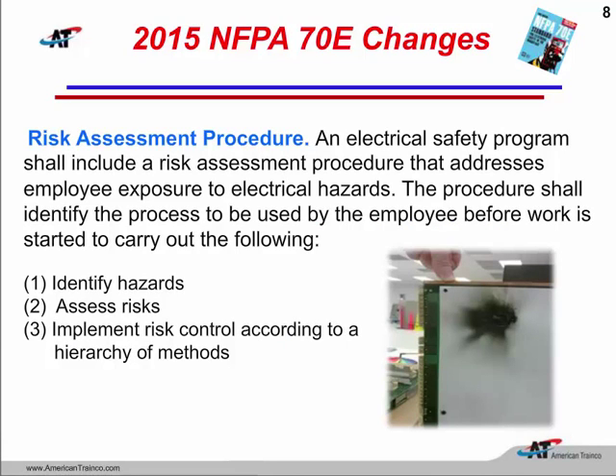So here's the risk assessment procedure. It does have to be included into the electrical safety program, and of course we're going to have to first identify the hazards. So we've got to take a look at the piece of equipment that we're about to approach, and we have to make a determination: is there any shock, arc flash, or arc blast hazard? At the same time, we want to really identify all the hazards, the mechanical hazards, chemical, whatever else there might be. Then we've got to assess the risks. So in Annex F, they're going to give us a method how to do that. There will be a table there to give us an idea that if there are exposed energized conductors or parts, what the risk might be as far as shock or arc flash is concerned.